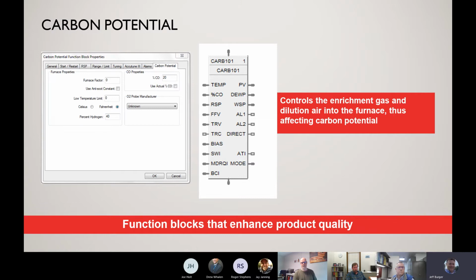We talked a little earlier about some of the specific function blocks for different applications. This is a very powerful tool because if you're an OEM or an end user with a heat treat facility that has carbon potential control, there is a function block in the library of the HC900 that is specific for that application. In other PLCs from other manufacturers, you have to do a lot of extra configuration or use multiple function blocks to accomplish this one task. But in the HC900, this is a standard function block that you can pull out into an open configuration worksheet and, really within no time at all, configure a carbon control loop and get up and running.